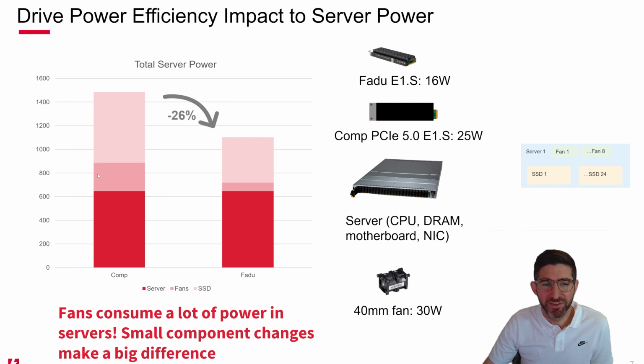But the thing that's not obvious is that the fan speed reduction has a very big impact on server power, because you don't have to run the fans at 100%. The fans will run at whatever the hottest component in the server is. So if the SSDs are running at 25 watts and there are 24 of them, the fans will run at 100%. And if you're running at a lower TDP, you can tune it to figure out the right fan speed. If you can tolerate a higher operating temperature on the SSD, then you can reduce the fan's power from 100% to about 30%. And in this example, I could actually reduce the total server power by 26% just by reducing the E1.S power from 25 watts to 16 watts. So again, it's not just the SSD power, it's also the SSDs and the fan.